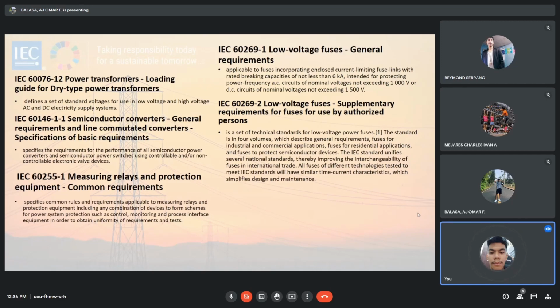When heat, which is mainly due to the transformer's losses, is transferred to the insulation system, a chemical process begins. This process changes the molecular structure of the materials which form the insulation system. The aging rate increases with the amount of heat transferred to the system. This process is cumulative and irreversible, which means that the materials do not regain their original molecular structure when the heat supply stops and the temperature decreases.